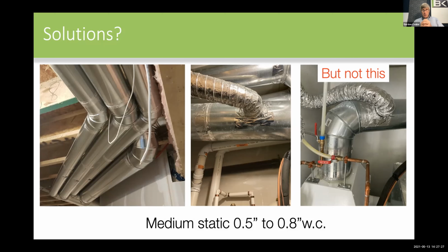So I'm good with that, especially when I air seal the ducts. Actually, when I air seal the ducts, the pressure is going to go up, which is nice. The pressure in the duct's going to go up because the air actually has to go all the way to the end run. So you're going to like that. What I don't want you to do is on the right-hand side. We see people using the high velocity, high static systems as a panacea. And I find them to be noisy and they're not working because people are taking shortcuts. They're not sealing the ducts. Notice the knuckles on that elbow. None of those are sealed. And you go, we don't need to seal an elbow. In a low static system running at 0.2 static, maybe not.